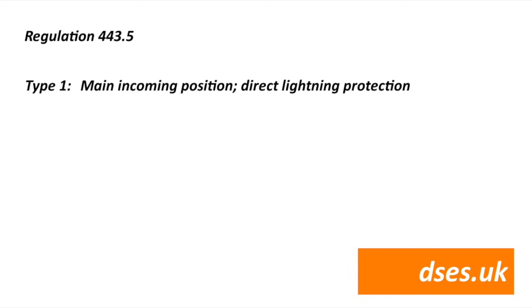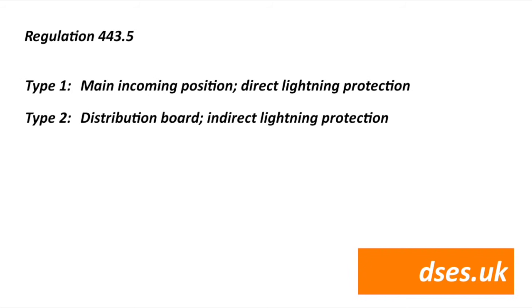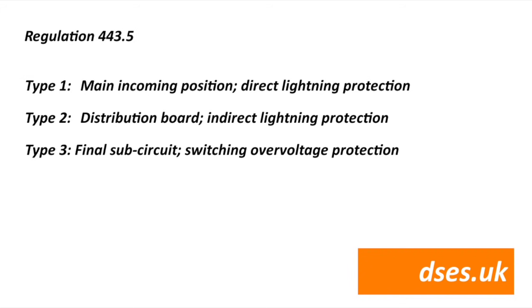But before we begin, it's important to understand that there are three different kinds of SPD. Type 1 would be located at the main incoming position and protects against a direct lightning strike. Type 2 would be at the distribution board and protects against indirect lightning strikes. Type 3 would be fitted to a final circuit or at an item of equipment to protect locally against switching overvoltages. That's the kind of overvoltage that may be caused by large inductive loads, such as motors and air conditioning.